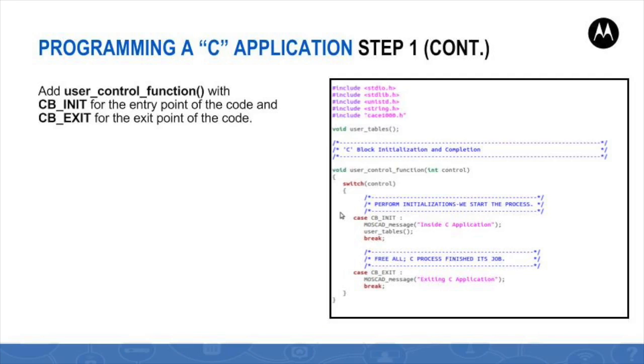A C process, like a regular computer program, requires certain setup initialization activities when it begins and certain cleanup completion activities as it exits. These activities may be triggered from the user control function. The existence of this function in the code is mandatory. However, it is not mandatory to perform initialization and or termination activities, which means that the CB_INIT or the CB_EXIT cases may be empty.